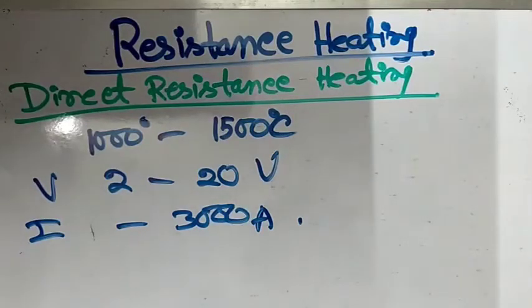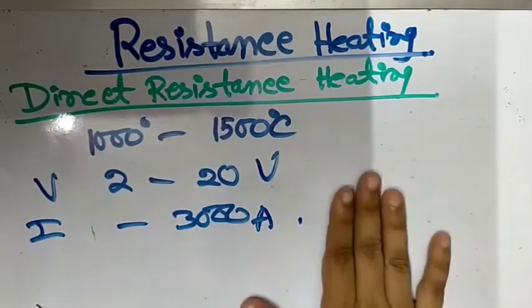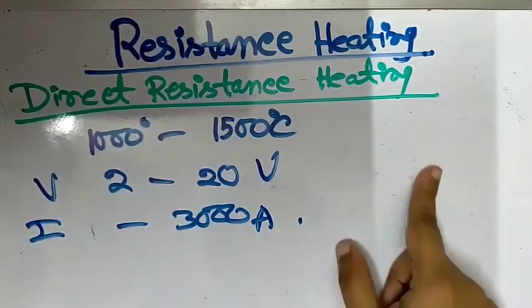Okay. Now, when highly conductive metals are to be heated, insertion of electrodes into charge would mean direct short circuit. And to avoid this, in such cases, highly resistive powder is sprinkled in between the surface of the pieces, and more heat is therefore produced at these contact surfaces. So this is all about direct heating. Now we discuss about indirect heating.